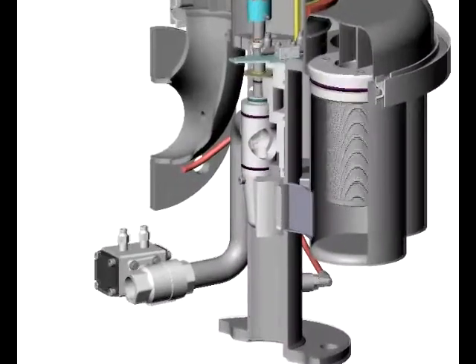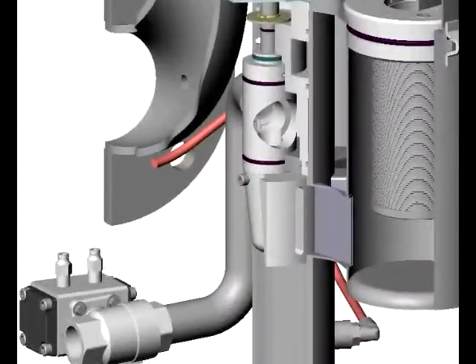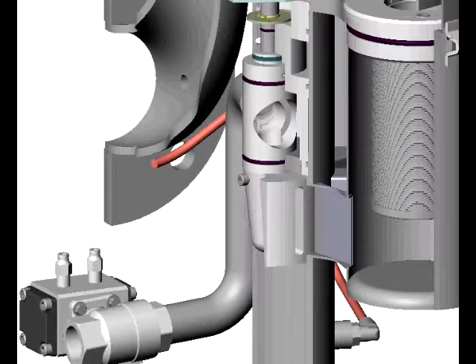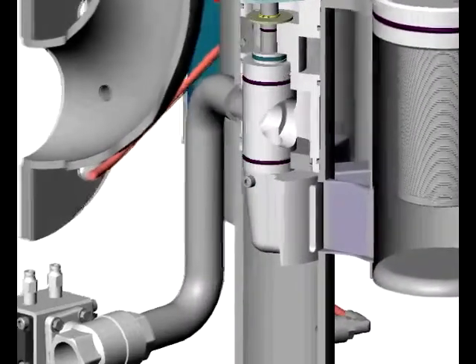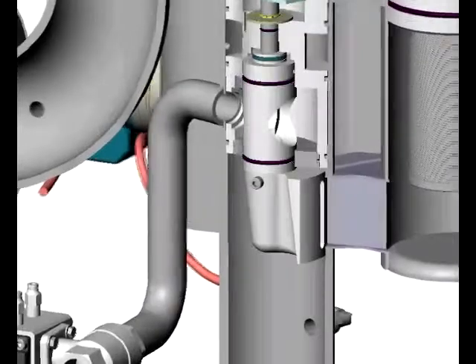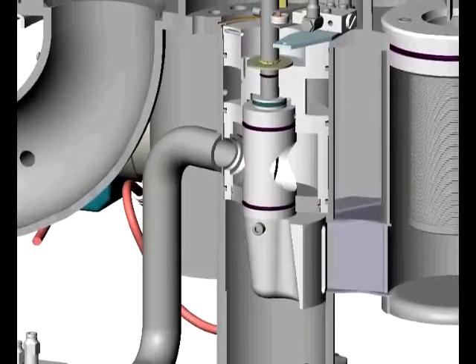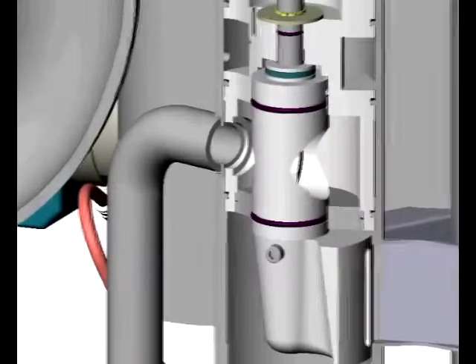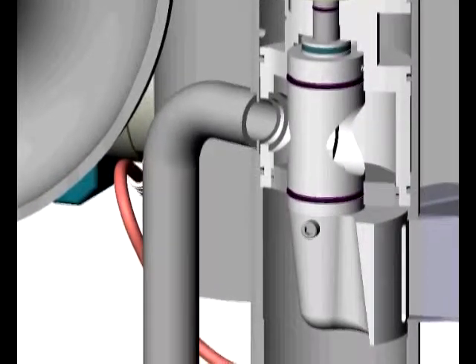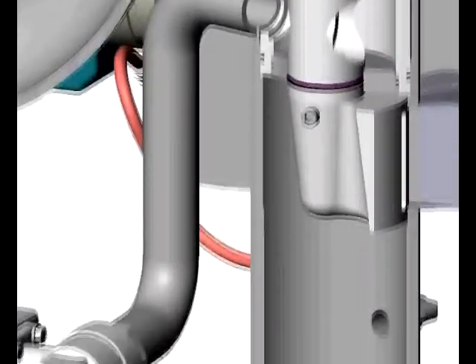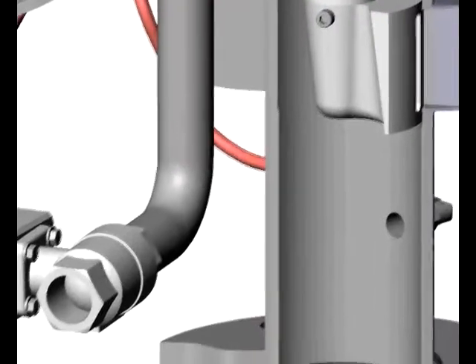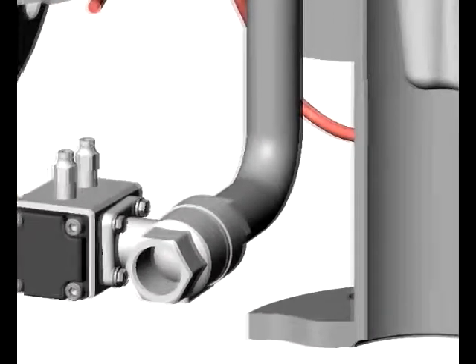We can now see that the face of the shoe has completely obscured the pod inlet gallery so that no fluid can enter. However, the vertical slot presents a new flow path for a small proportion of the common filtered fluid to pass down the inside of the filter element, flushing the accumulated debris into the shoe, up into the body of the indexing valve, along the three-quarter inch backwash pipe, and away to atmosphere via the backwash valve.